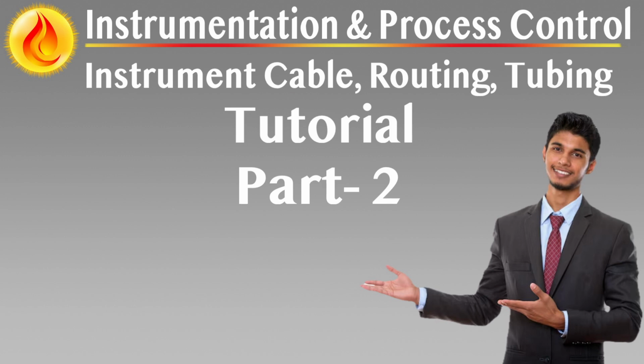Cables entering the building must pass through fire and water-sealed wall sleeves that meet EMC shielding requirements. The routing under the cavity floor must preserve segregation rules defined for safety, signal class, and functionality. Due to limited underfloor access, traditional tray systems are not practical. Instead, cables should be bundled and logically grouped using color-coded or labeled harnesses for simplified identification and maintenance. The cable entry design must reserve at least 20% spare space to accommodate future system modifications.